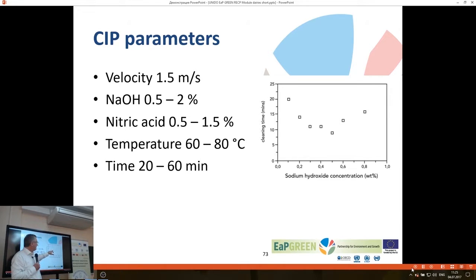Below, cleaning effect was less. You needed to allow longer time. But above this optimum, the same was true. So at 1% or 2% caustic, cleaning time actually would have increased in comparison to the optimum. So this is an important observation, because there is such an optimum. More concentration does not necessarily improve the cleaning effect, and this is a strong advocate for this dosage equipment, so that we actually stick to the optimum concentrations and do not allow more or less.